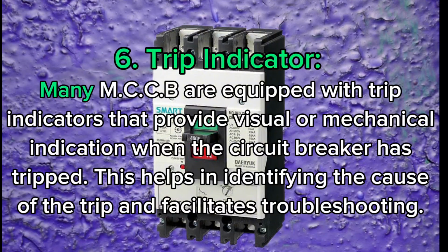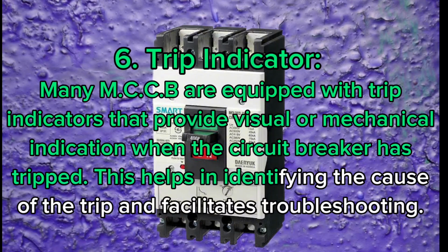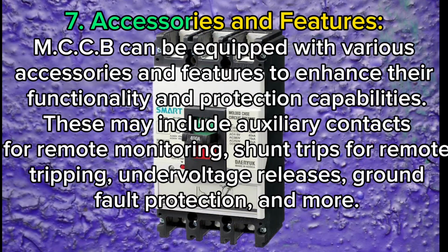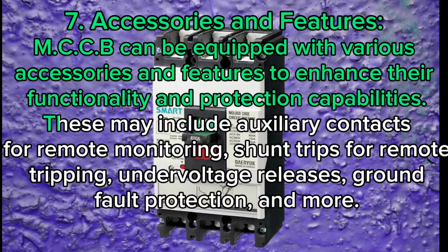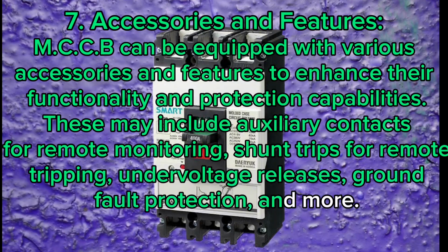6. Trip indicator. Many MCCBs are equipped with trip indicators that provide visual or mechanical indication when the circuit breaker has tripped. This helps in identifying the cause of the trip and facilitates troubleshooting. 7. Accessories and features. MCCBs can be equipped with various accessories and features to enhance their functionality and protection capabilities. These may include auxiliary contacts for remote monitoring, shunt trips for remote tripping, undervoltage releases, ground fault protection, and more.